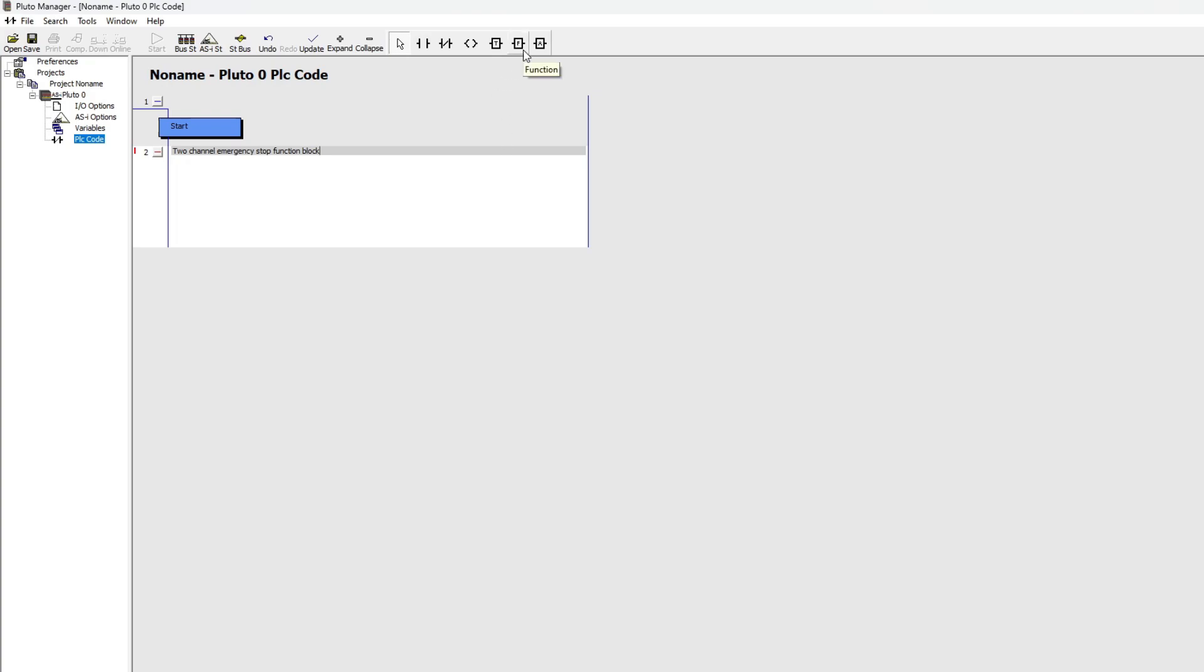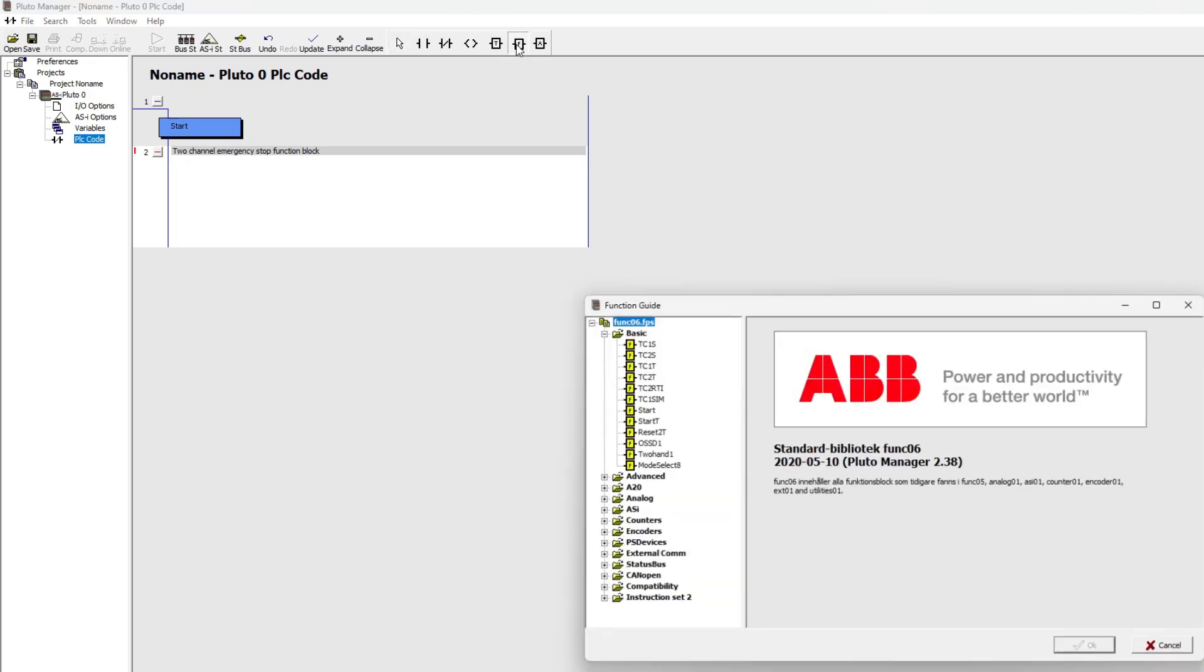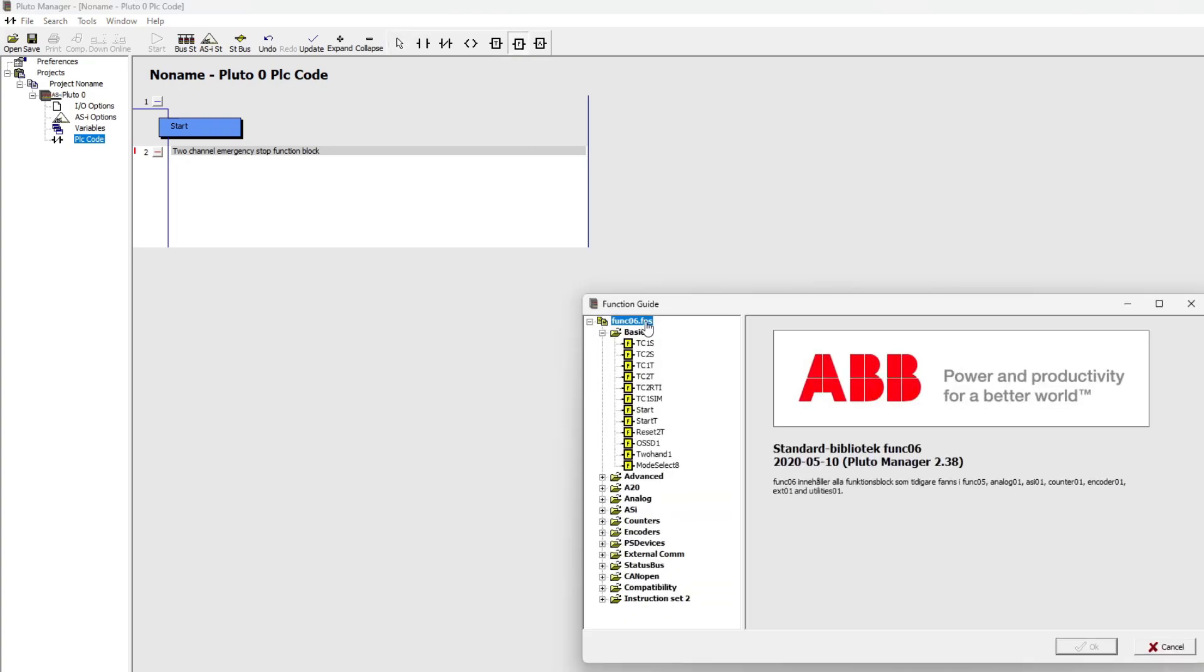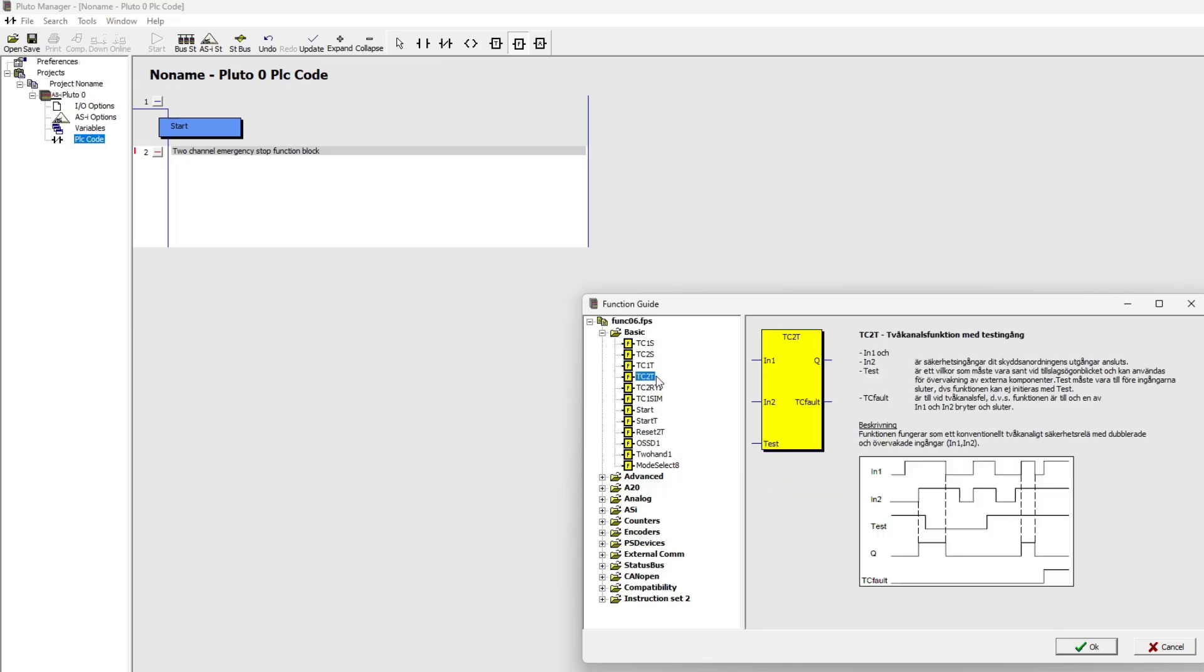I will add a TC2T function block to my first programming rung. It works as a conventional two-channel safety relay with duplicated and monitored inputs. To the two in channels we will add our inputs from the emergency stop.